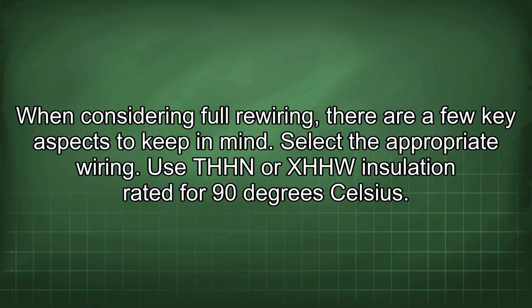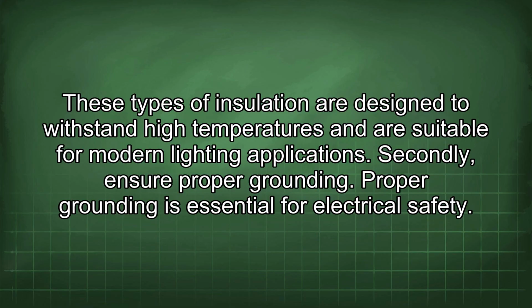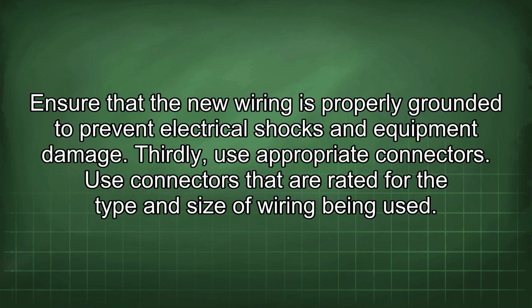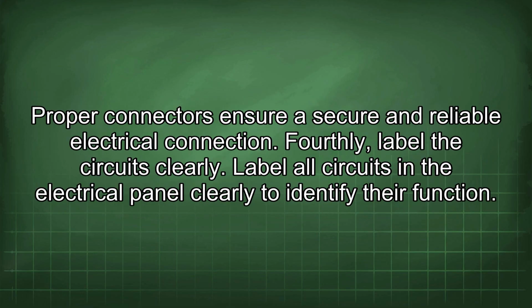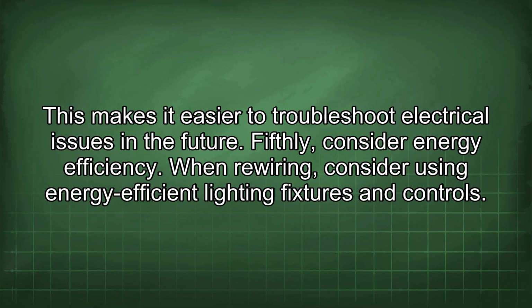Select the appropriate wiring. Use THHN or XHHW insulation rated for 90 degrees Celsius. These types of insulation are designed to withstand high temperatures and are suitable for modern lighting applications. Secondly, ensure proper grounding. Proper grounding is essential for electrical safety. Ensure that the new wiring is properly grounded to prevent electrical shocks and equipment damage. Thirdly, use appropriate connectors. Use connectors that are rated for the type and size of wiring being used. Proper connectors ensure secure and reliable electrical connection. Fourthly, label the circuits clearly. Label all circuits in the electrical panel clearly to identify their function. This makes it easier to troubleshoot electrical issues in the future.